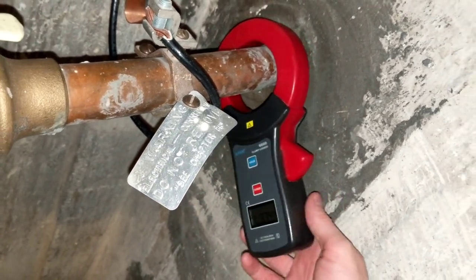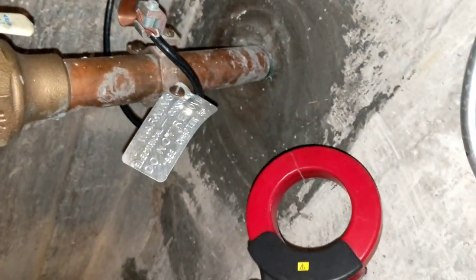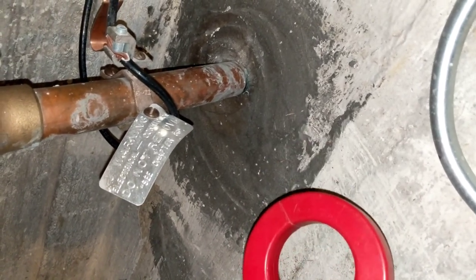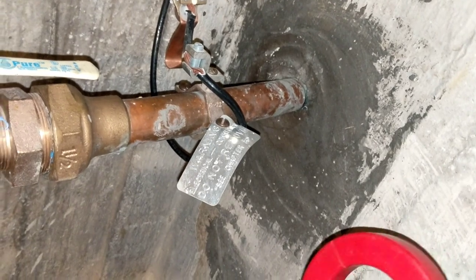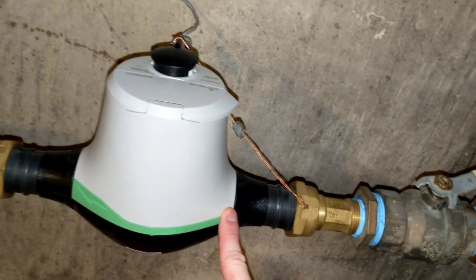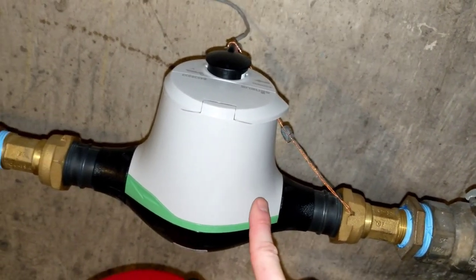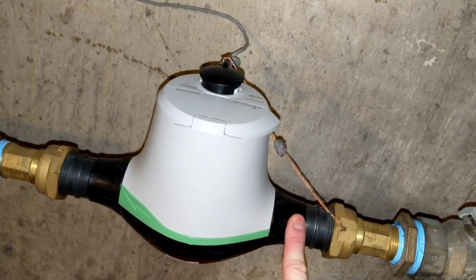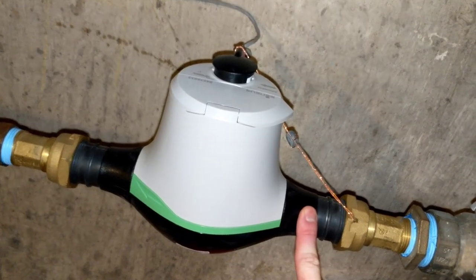That is 380 milliamps of AC electrical current from the power grid and/or neighbors — primary and secondary neutral current. It's not going out to the street here because we have a plastic water meter, which acts as a break, an electric break, which is exactly what we need.